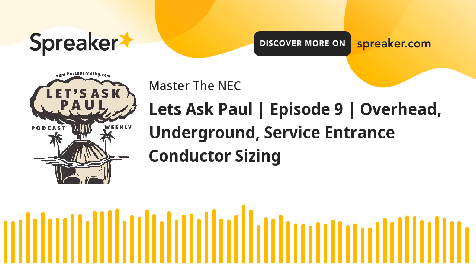Okay? So let's look at the general first. 230.23(A) says, conductors shall have a sufficient ampacity to carry the current for the load as calculated in accordance with Article 220 and shall have adequate mechanical strength. Of course, these are overhead service conductors, so they are from an overhead supply. So, obviously mechanical strength, how they're supported on messenger or whatnot, that type of thing. But when it comes to, again, sufficient ampacity, it gives us that direction to Article 220. So you have to do a calculation. Whether you're doing the standard method or the optional method, you still have to do a calculation.